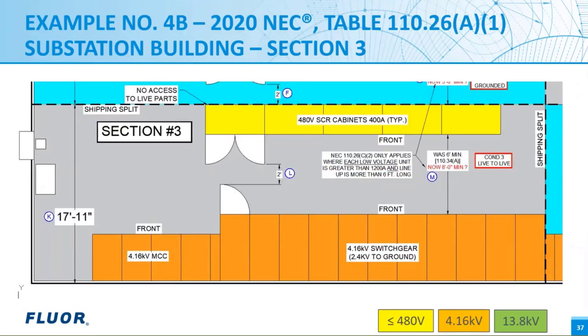Now, here's where things start getting a little stickier, strictly looking at it from a code perspective. Prior to the 2020 NEC, all that was required for the minimum distance shown near bubble M between the 480 volt SCR cabinets and the 4160 medium voltage gear was 5 feet, based on table 110.34(A), for condition three, where you're exposed live parts to exposed live parts, where the equipment with the higher voltage to ground was 2400 volts. But 110.32 also requires that the doors of the equipment must be able to open 90 degrees. So normally we would have probably made the minimum dimension near bubble M a dimension of 6 foot anyway, to allow the doors on both sides to open a full 90 degrees. Again, since these 480 volt SCR cabinets are only rated 400 amps each in their individual cabinets, in my opinion, we still only require 6 foot minimum.